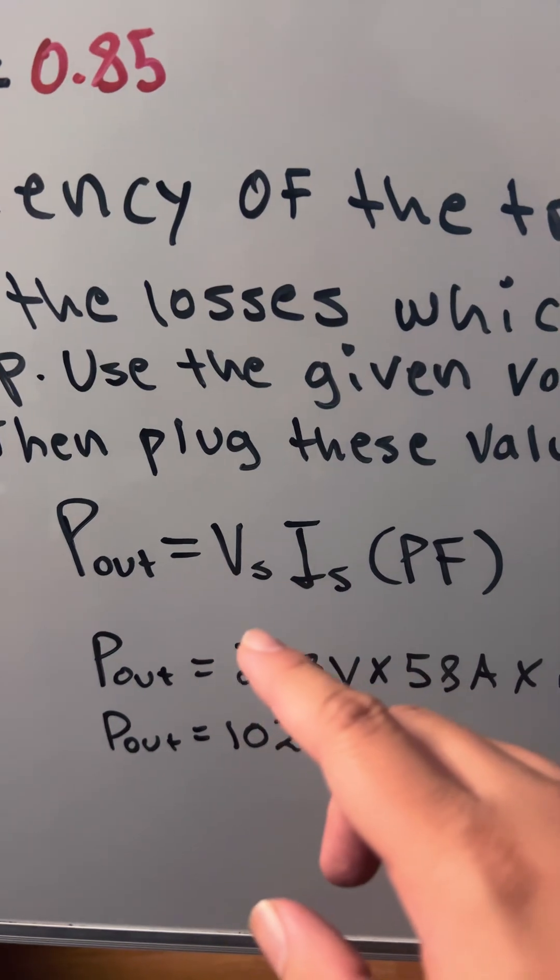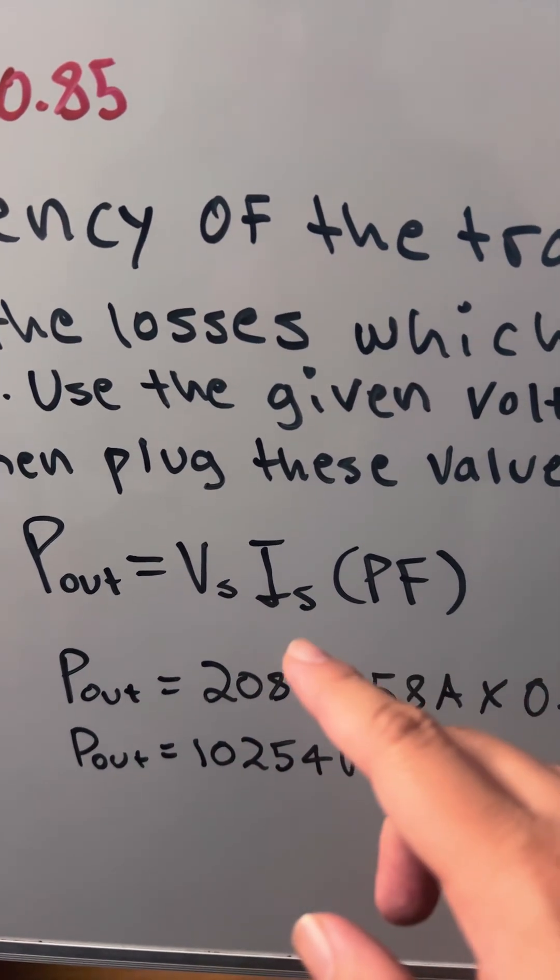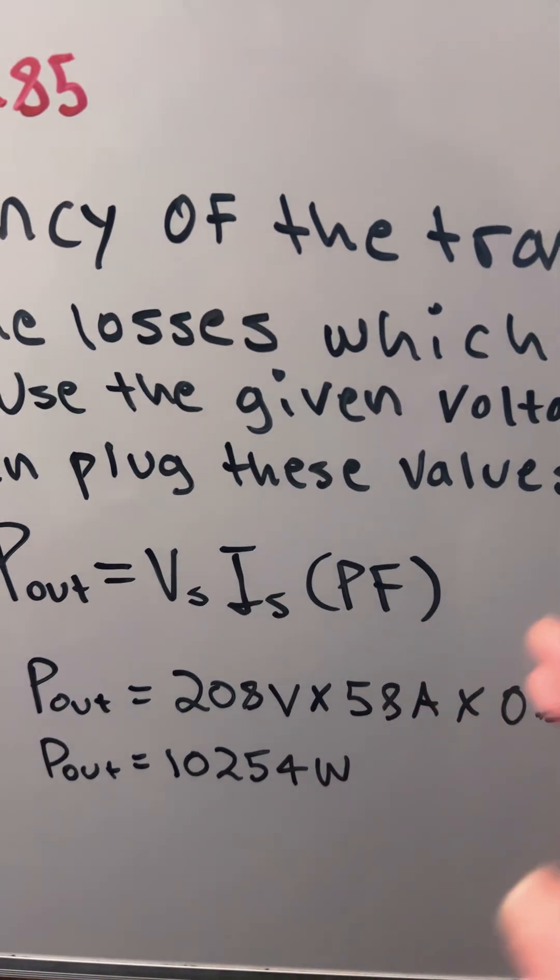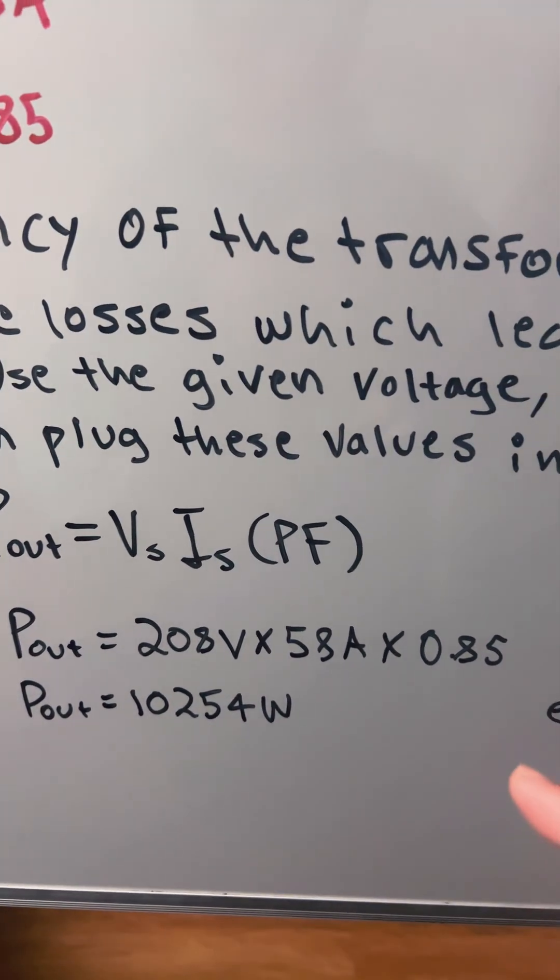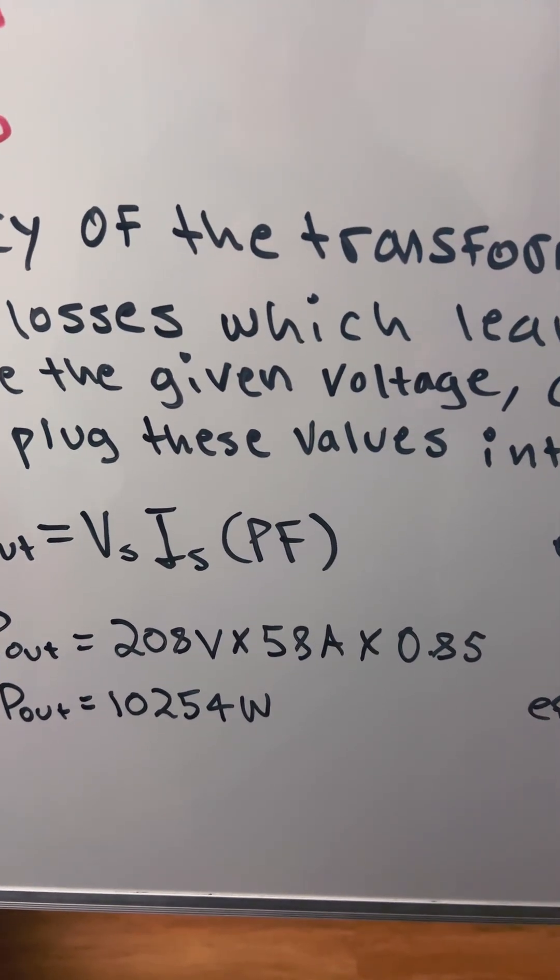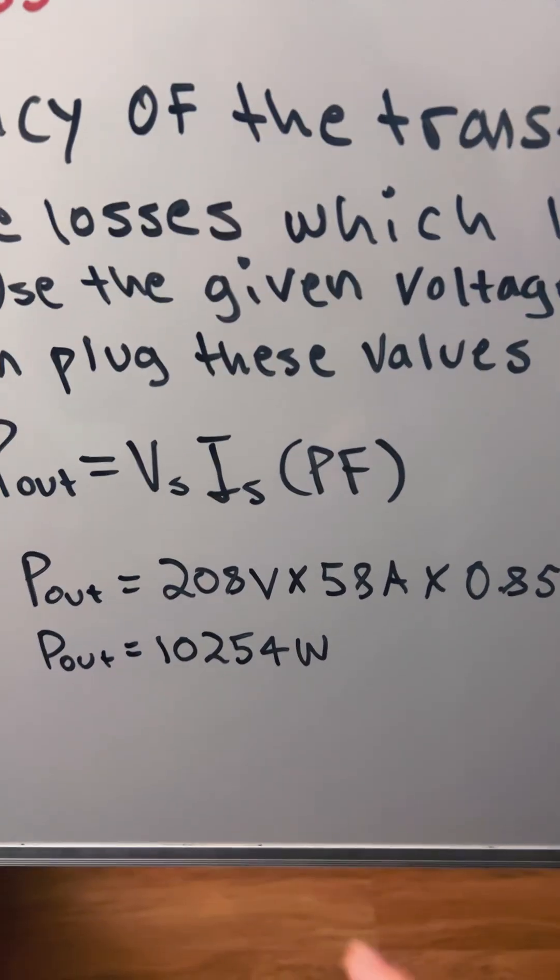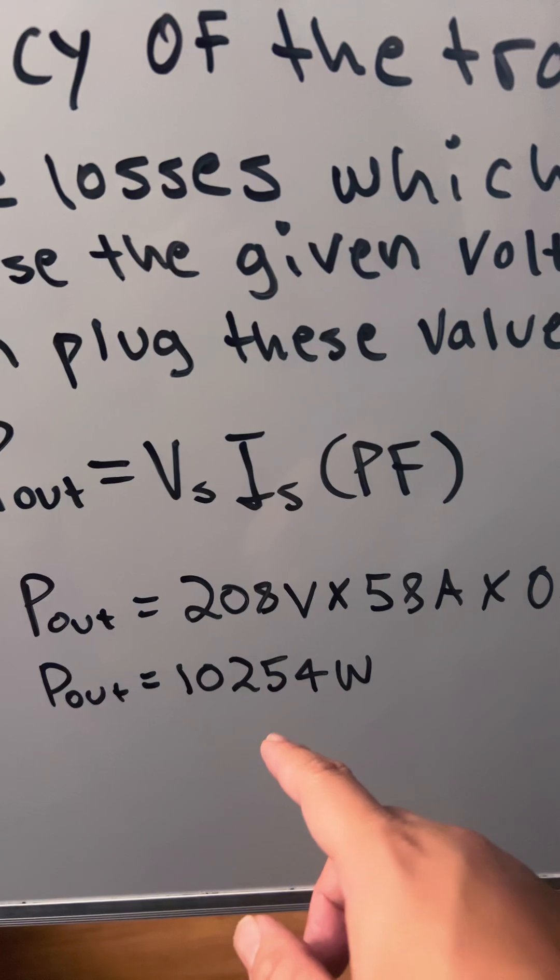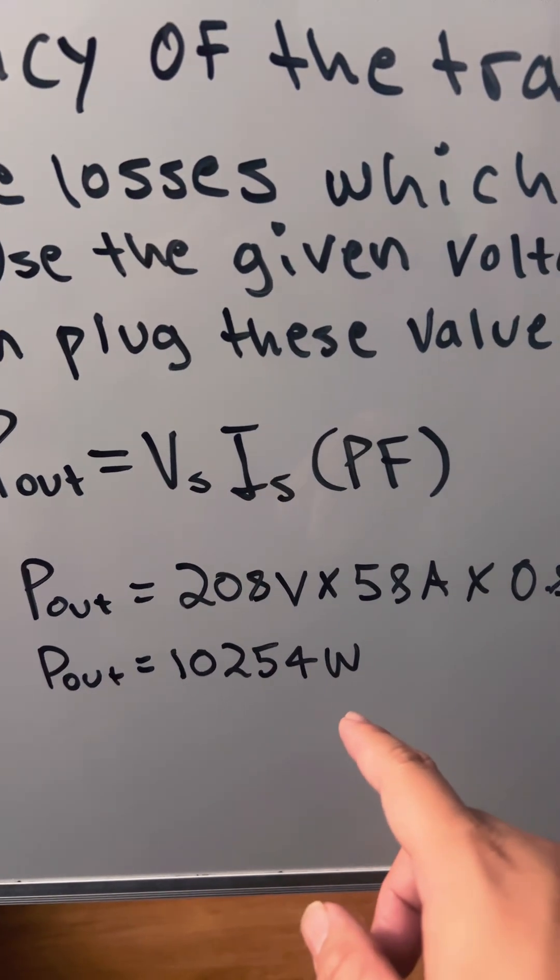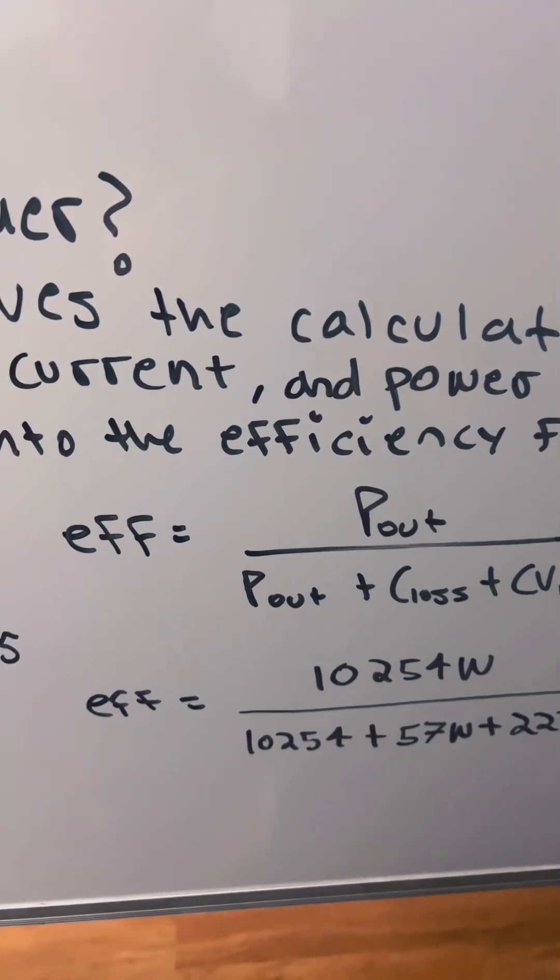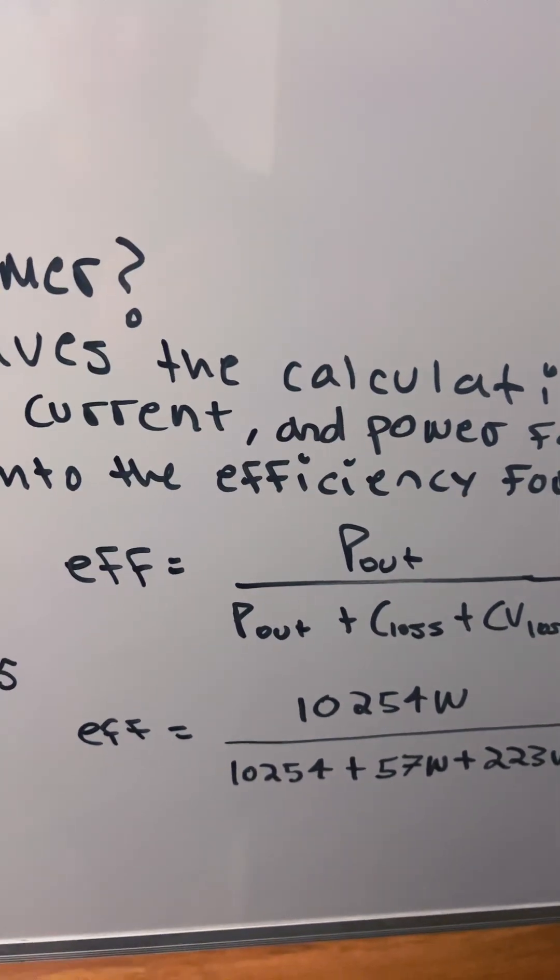P_out equals the secondary voltage times the secondary current times the power factor, so it's 208V × 58A × 0.85, which gives us 10,254 watts. For the final step, we're going to calculate the efficiency.